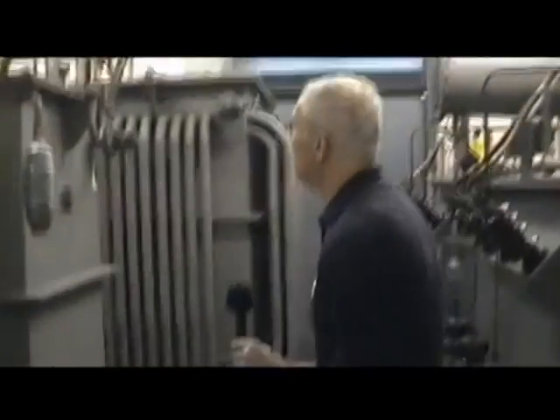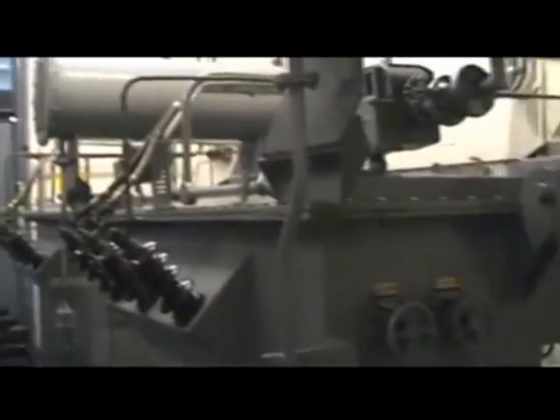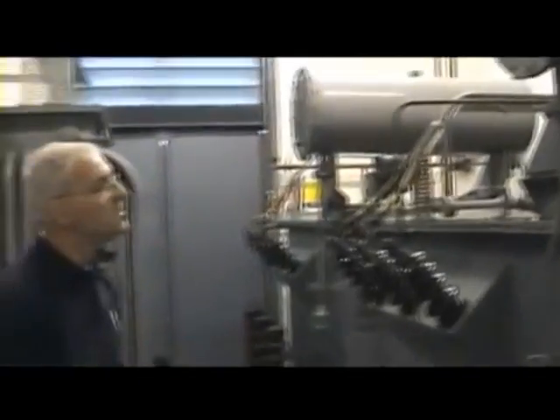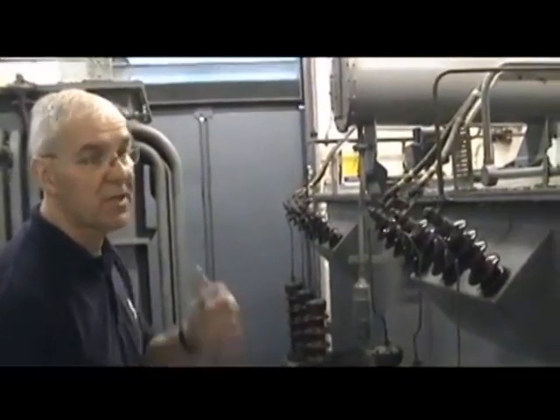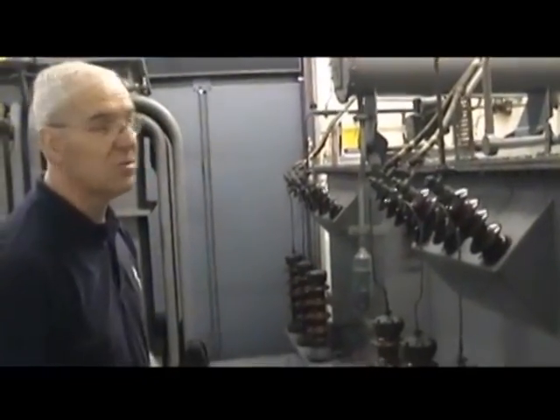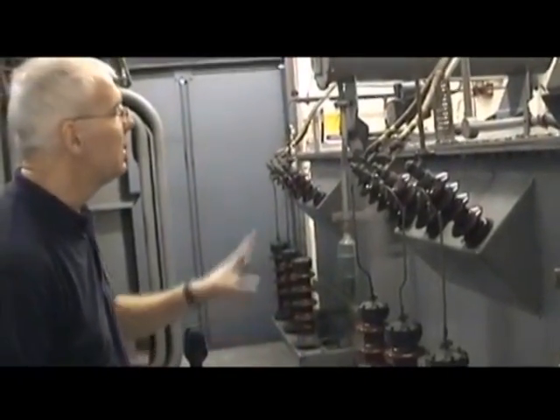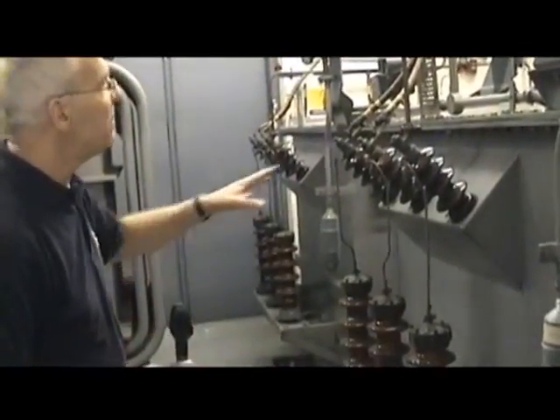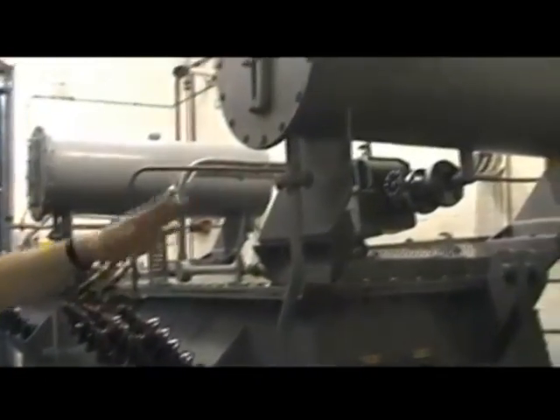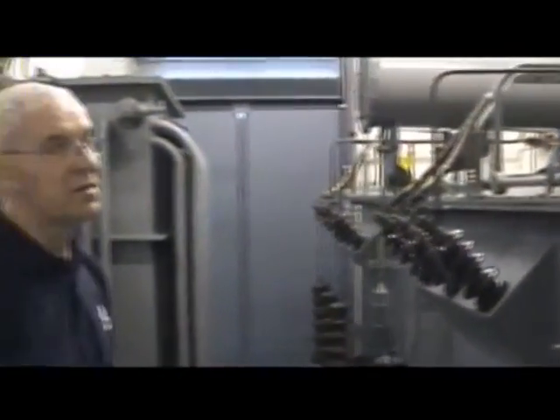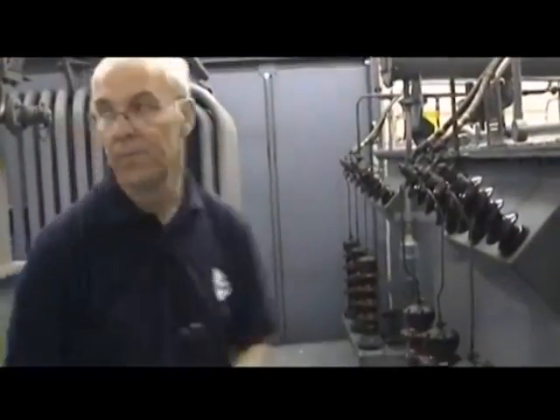And this is the sort of oily, smelly type area where the transformers live. The mains transformers, actually, because there are two of them, are here. These take 11 kV, 11,000 volts AC from the national grid, and drop it down to about 10,000 or 9,000 volts. Two of them, and we feed the 9,000 volts or so via these copper bars here through to a solid state rectifier, which replaced a mercury arc rectifier. So it's a solid state rectifier just the other side of the door, which then generates the DC. So that's the mains transformers.